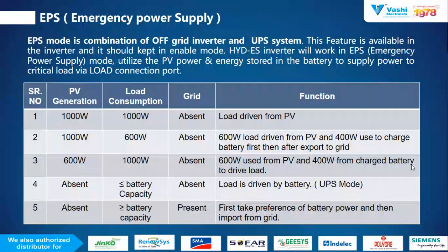It means UPS system. So in this table, we consider the first 3 points as grid absent mode, which means it will work as off-grid mode. And the fourth and fifth we consider as UPS mode or EPS mode. To give an easier briefing, I made another table considering PV generation, load consumption, and grid availability or not. According to that, the inverter will function.